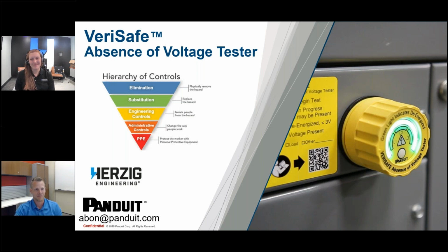So thank you. There's a lot of information there. There's going to be some redundant information, but I think it's going to make sense. I'll cruise through it pretty quick because Caitlyn already went through it in very good detail. So VeriSafe. VeriSafe, the absence of voltage tester, as Caitlyn pointed out, is a different method to confirm the absence of voltage. When you think about the hierarchy of controls, it's not PPE. It's not an administrative control like work instruction or signage. It's more of an engineering control, which is designed to isolate hazards from people. It's not substituting or eliminating the electricity. It is controlling the exposure.